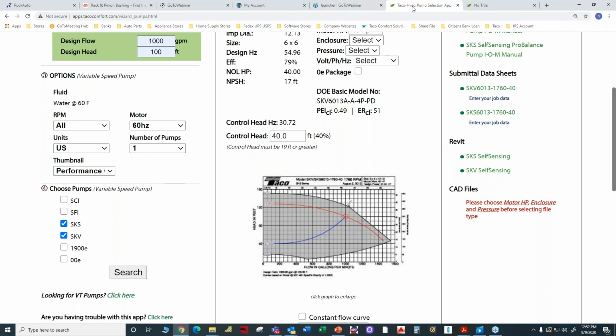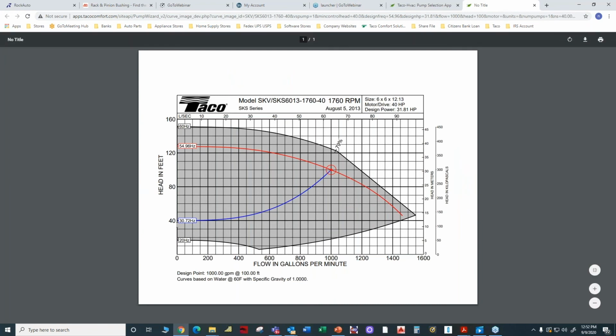So that looks like this on the pump curve. So there's the 40 feet. There is 1,000 gallons per minute at 100 feet of head. So this value up here is the design operating point, and this value over here is the control head. Now, if you notice how flat the curve is, for all practical purposes, between 0 and 200 gallons per minute, it's virtually flat at 40 feet. Fairly typical of this type of curve. Okay, so let's assume my minimum flow is 15% of my design flow. In this case, it would be approximately 150 gallons per minute. Well, there would be 100, 150, and that would be 40 feet.